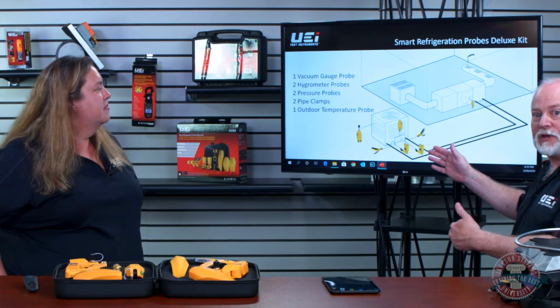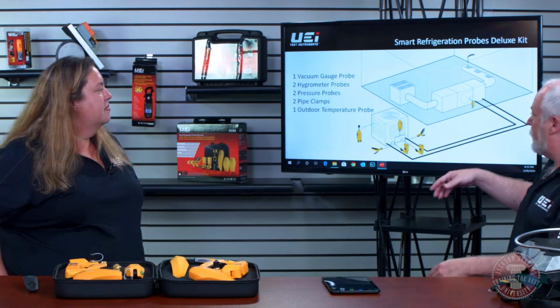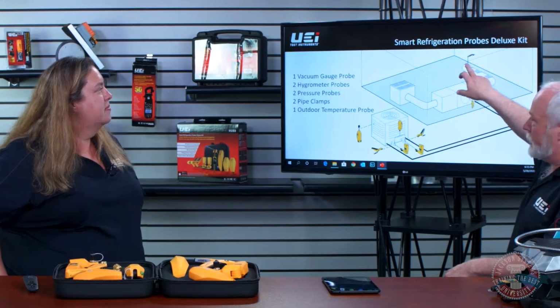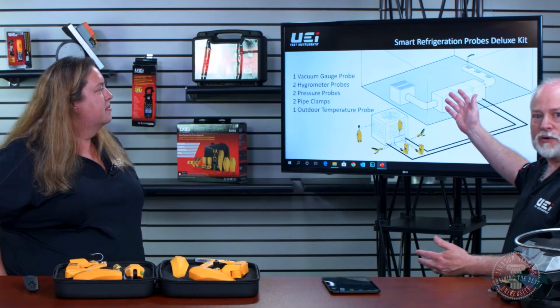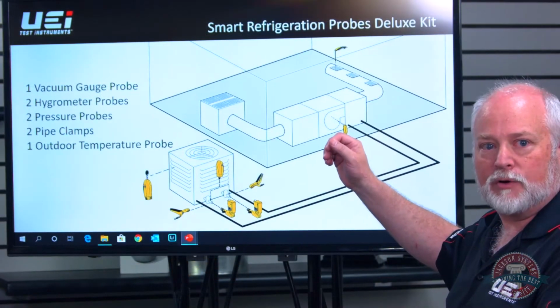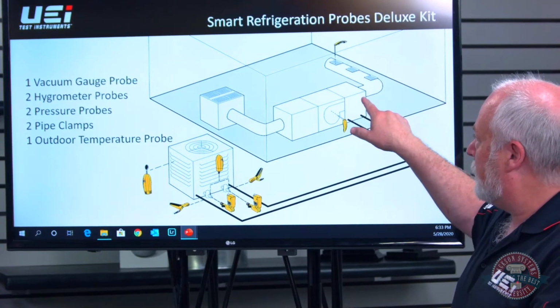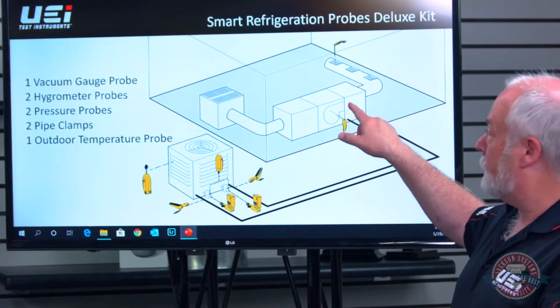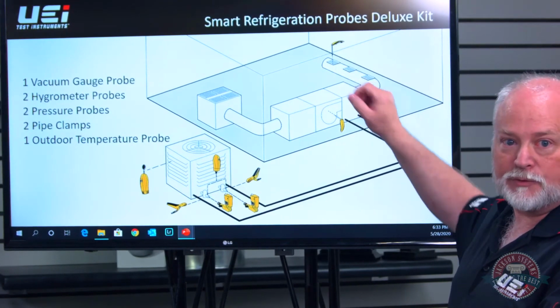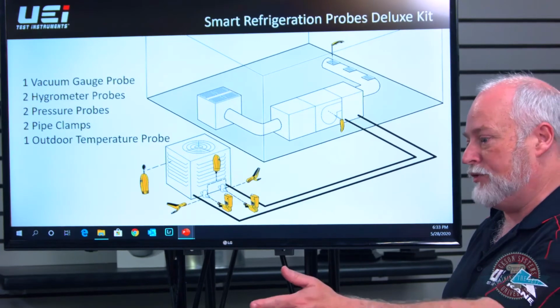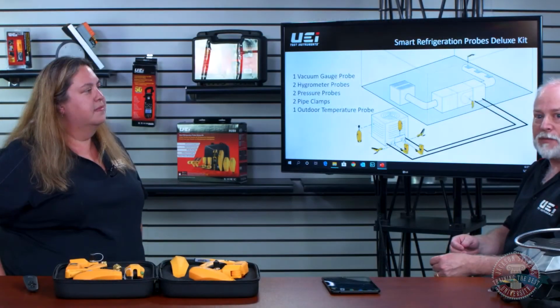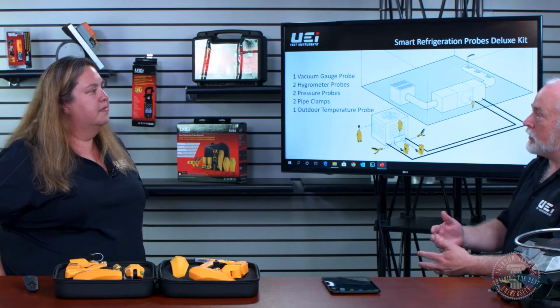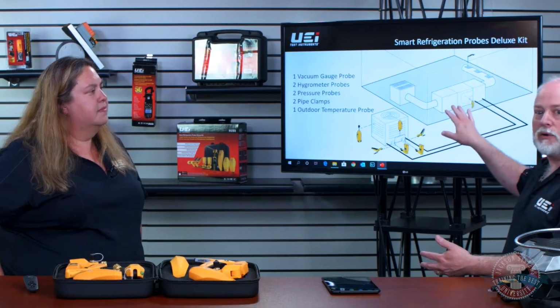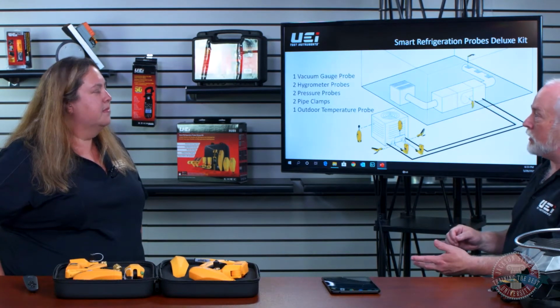For using this, we're setting up a furnace with just our air probes. Because if I put this down here, maybe I'm only getting a 12-degree drop across my evaporator coil. Or if I put it down here, maybe I was getting 18 degrees, but I picked up a lot of heat going through this ductwork. One thing these will calculate, as we'll show in the app, is enthalpy, so the closer you are to that coil, the more accurate those calculations are going to be.